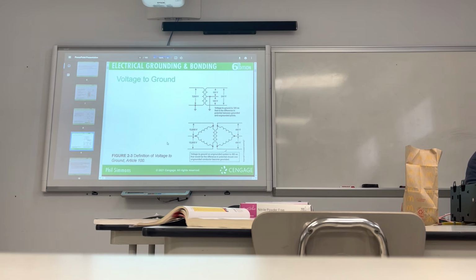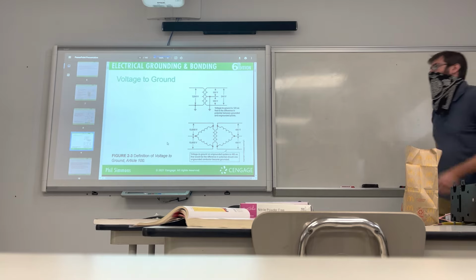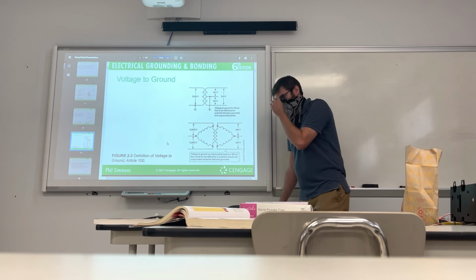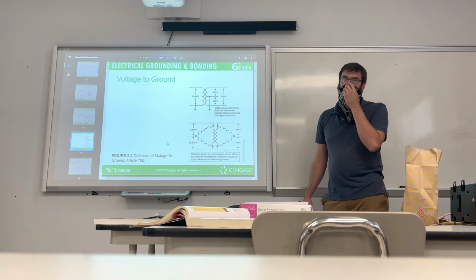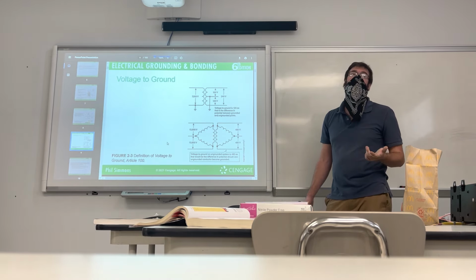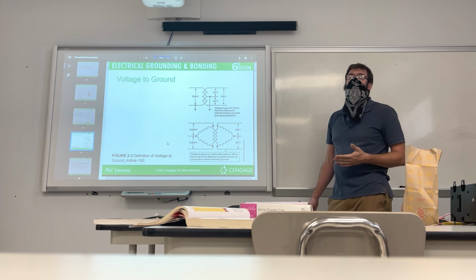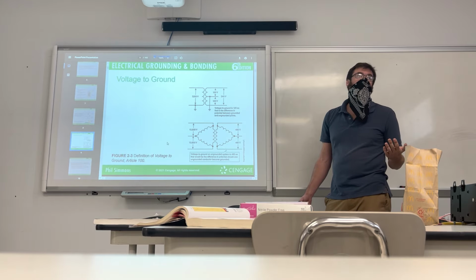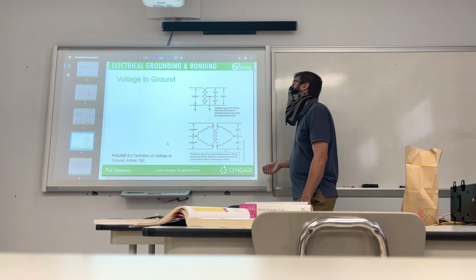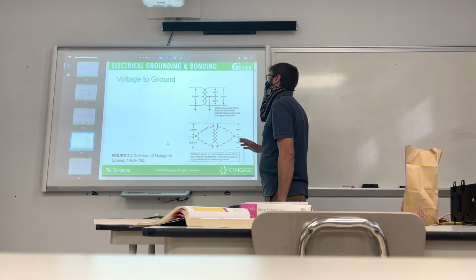Why this is a terrible slide. Yeah, I'm not sure what they're trying to get at, volt to ground. I know there's a 250 volt limit that if you have 250 volts or more from a single leg to ground, then all your conduit has to be grounded with bonding bushings. I'm not sure what they're trying to get at here. But just so you know, this is the breakdown of a common system.